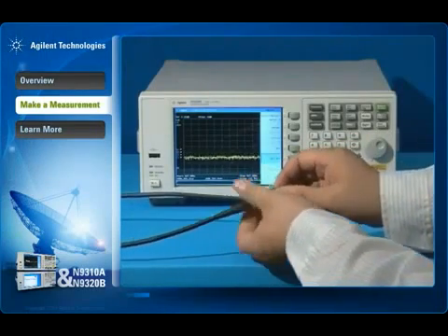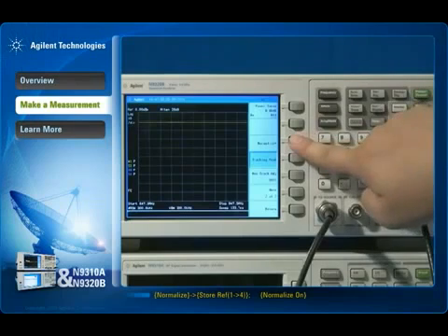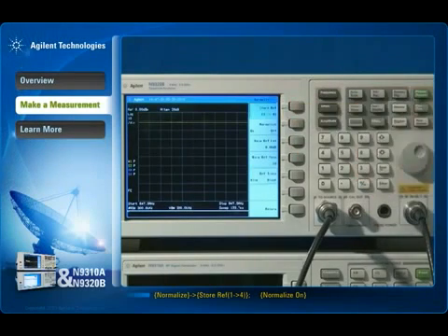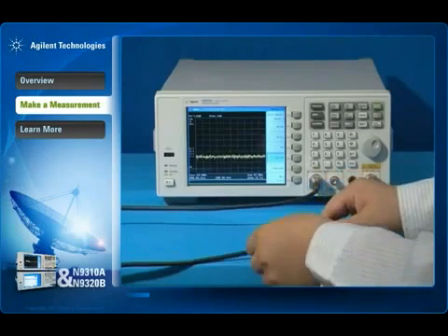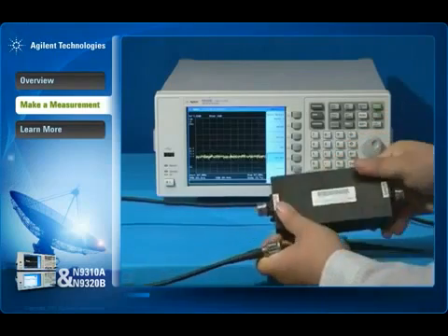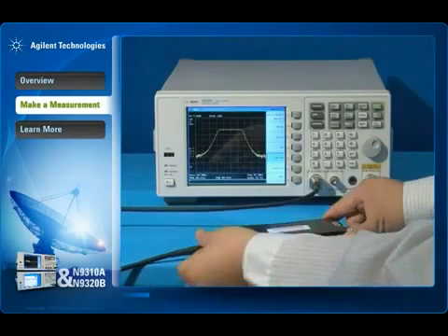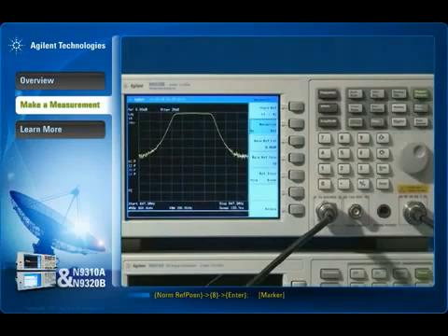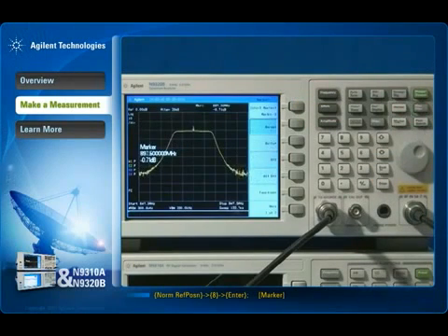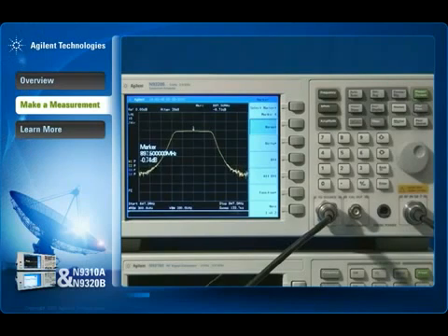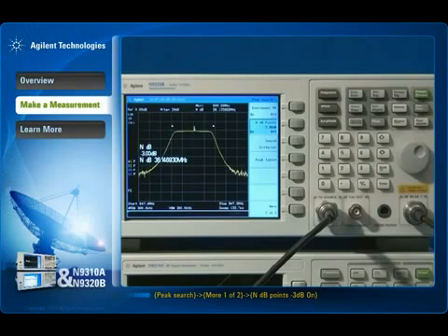Connect the cable from the tracking generator output to the analyzer input. Next, store the frequency response in trace 4 and normalize to eliminate the effect of the test environment. Reconnect the filter to the analyzer input and change the normalized reference position. The marker readout displays the insertion loss of the filter at specific frequencies. The N9320B also provides a straightforward way to measure the 3 dB bandwidth of your DUT with just one button press.